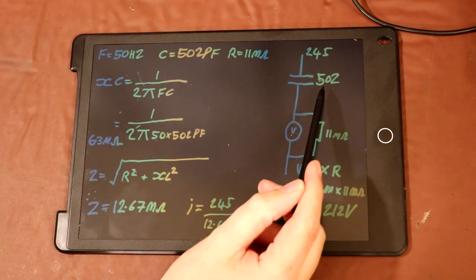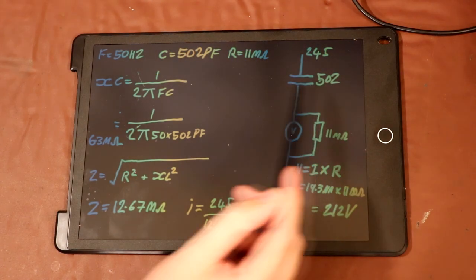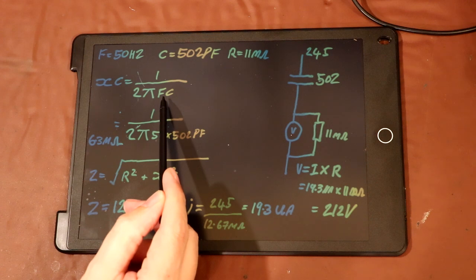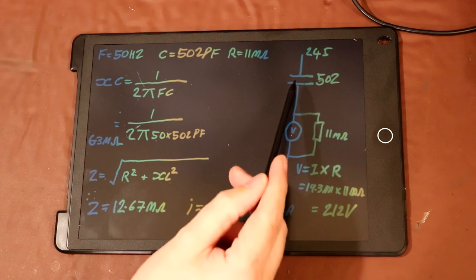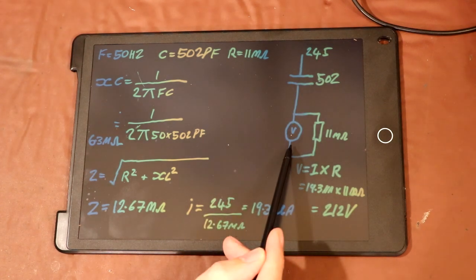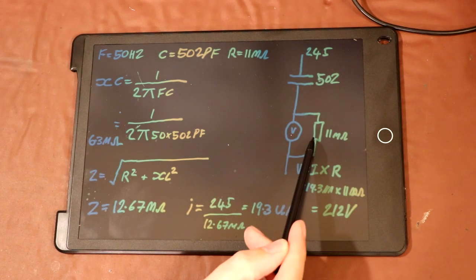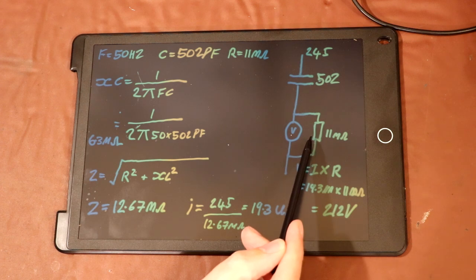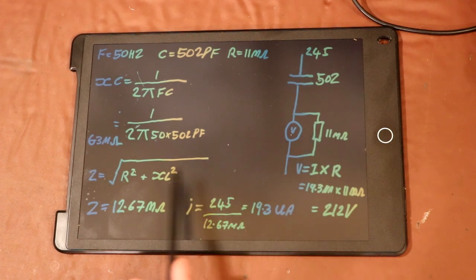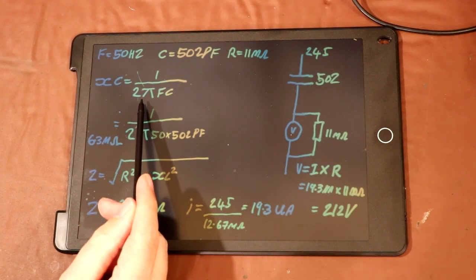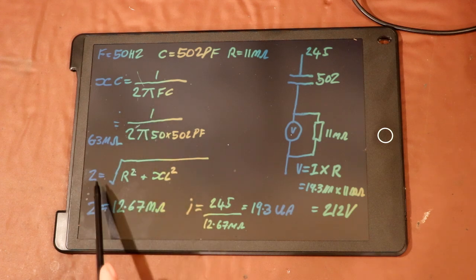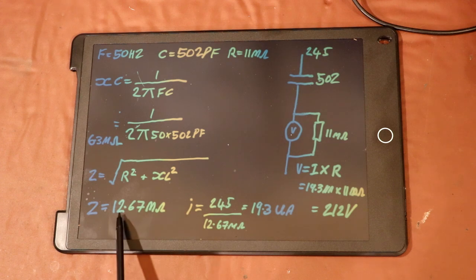If we know the value of the capacitance between the two conductors, we can work out what the reactance of the capacitor is. And what you'll find is the reactance of the capacitor here actually forms a potential divider with the input impedance of the voltmeter. In this case, the KAIWEETS meter has an input impedance of 11 megohms. So using that 11 megohms and also the value we've worked out for the capacitive reactance, we can work out the total circuit impedance, which as it happens works out to be about 12.67 megohms.